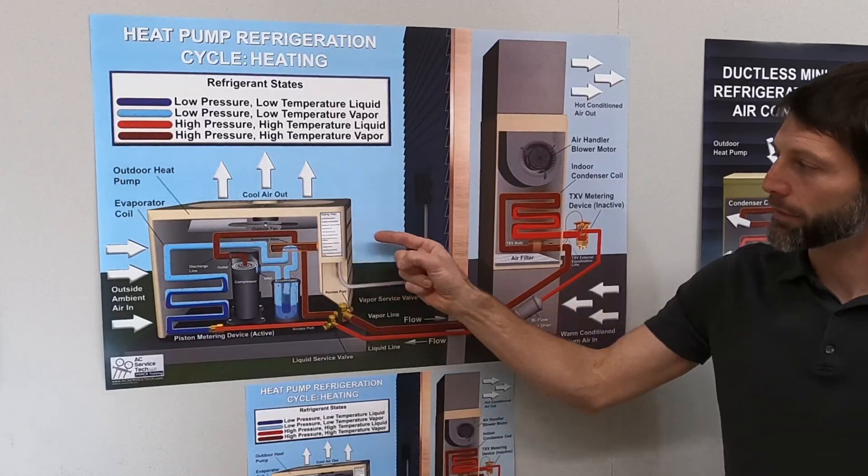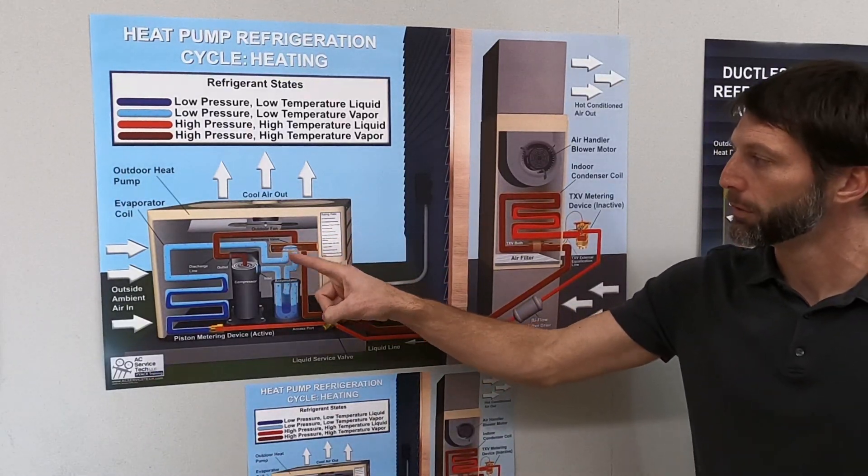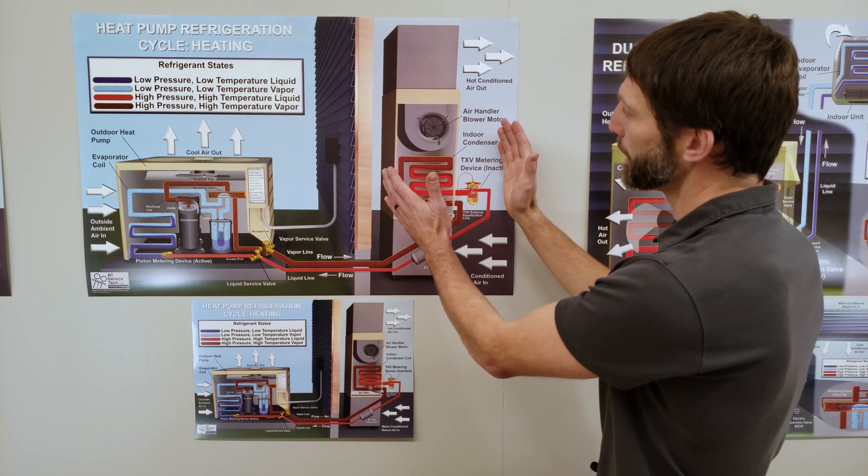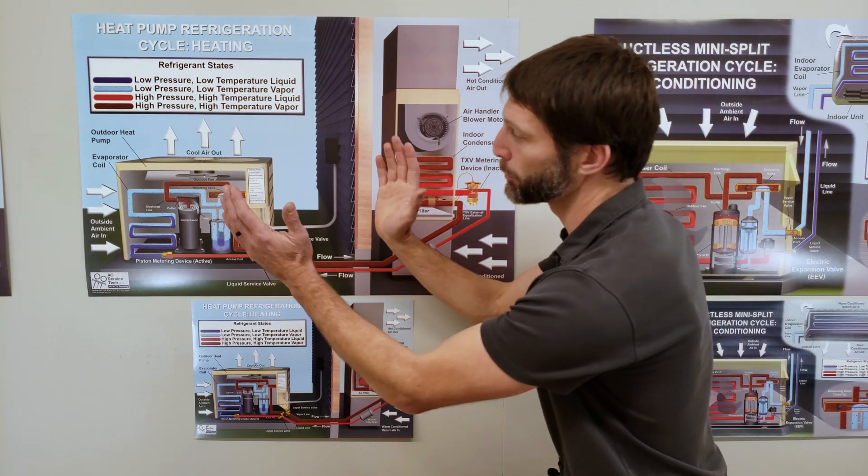Right here you have your reversing valve. It slid this way to connect the tube, the middle and the left tube right here. So you are rejecting heat inside from the refrigerant and you are absorbing heat outside.